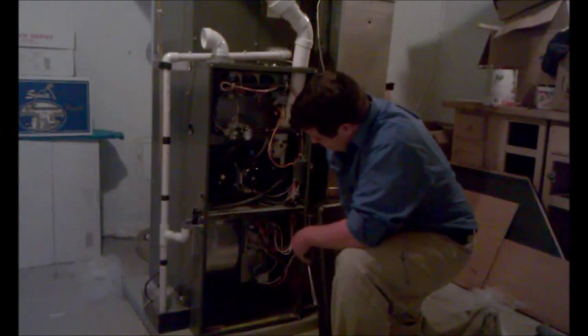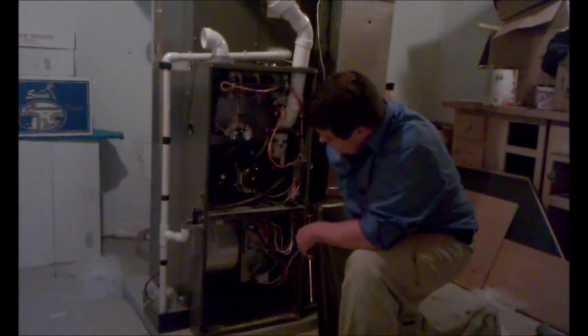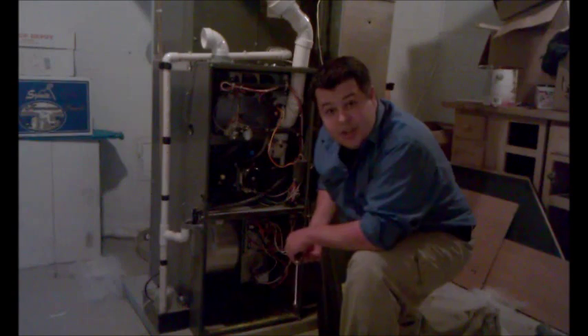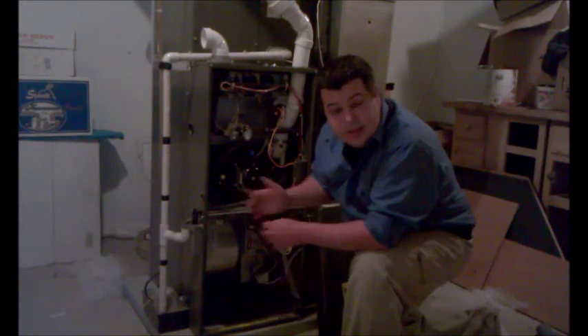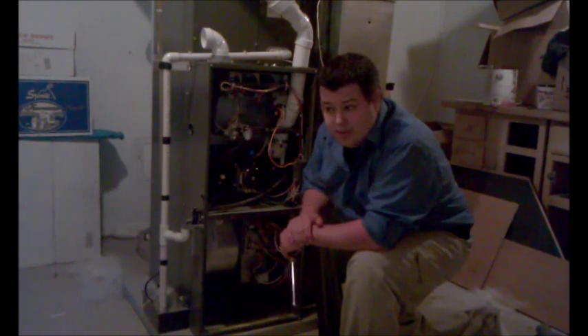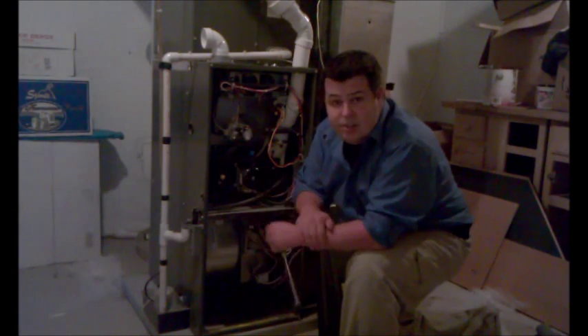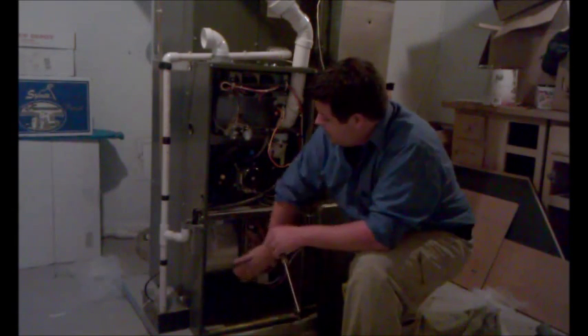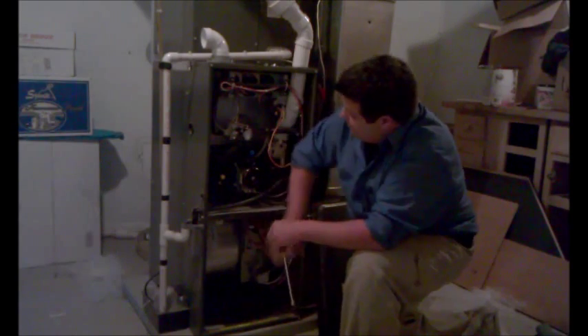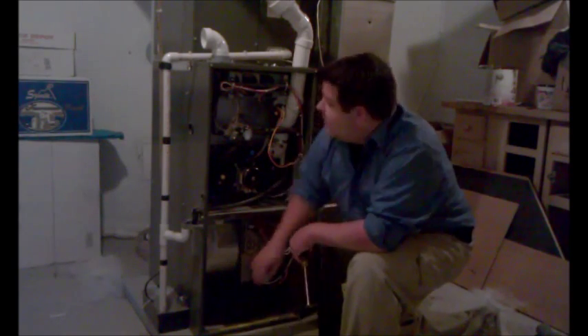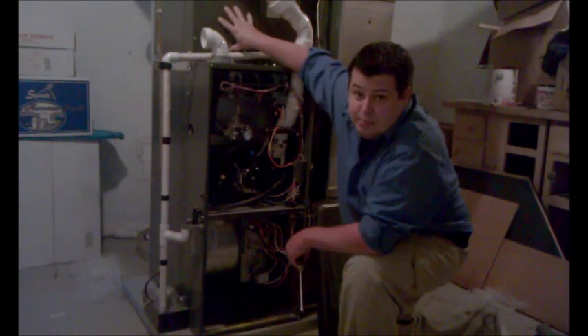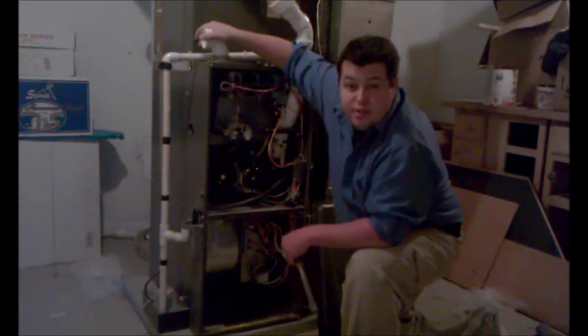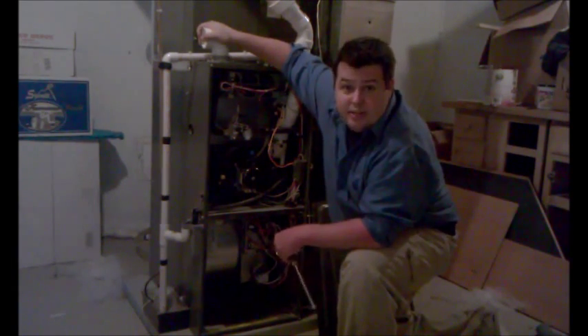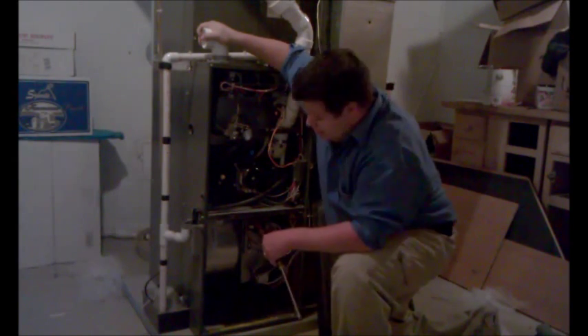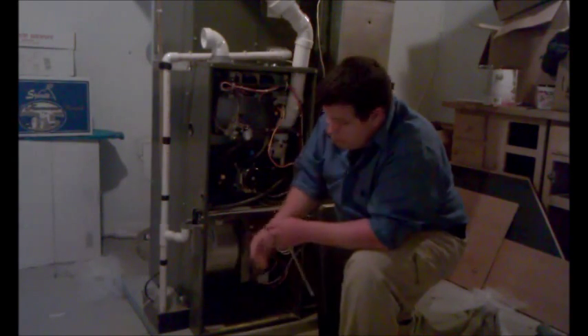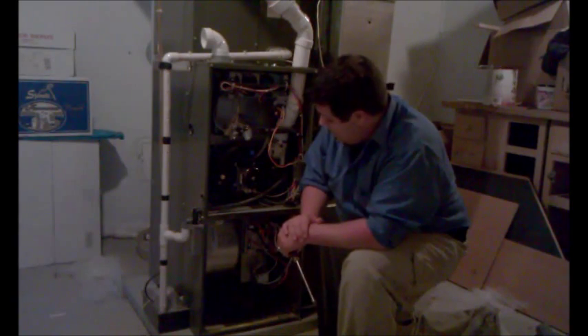We're checking the blower wheel, checking the capacitor, checking the bearings, the filter. Another thing is, if you don't change your filter, you really ought to, unless it's a year-long filter, because as the dirt moves through the system, it gets caught in the blower wheel. It can get caught in the evaporator coil at the top of the furnace or under the furnace, and it can end up overheating your furnace and cracking the heat exchanger. So we're checking the blower wheel, checking to make sure there's no dirt built up there, checking the bearings.